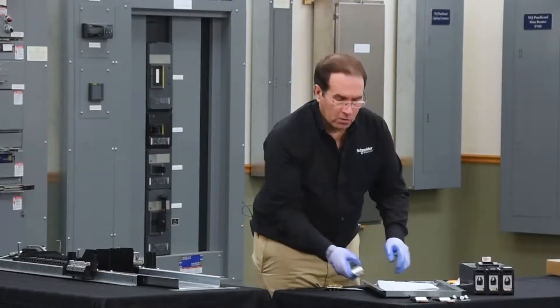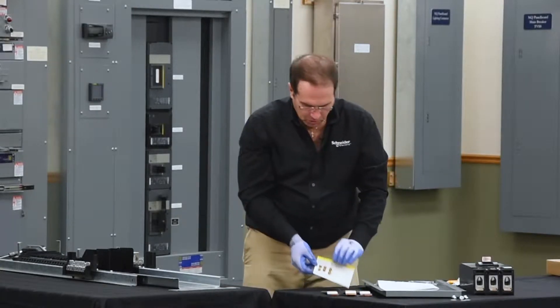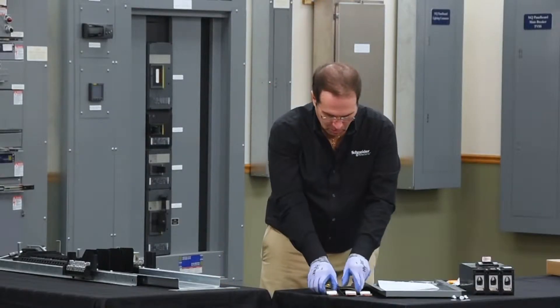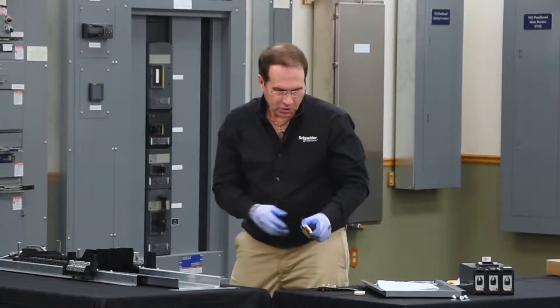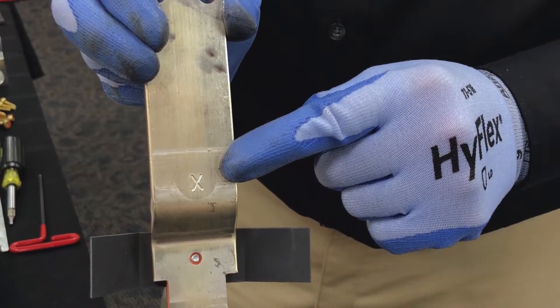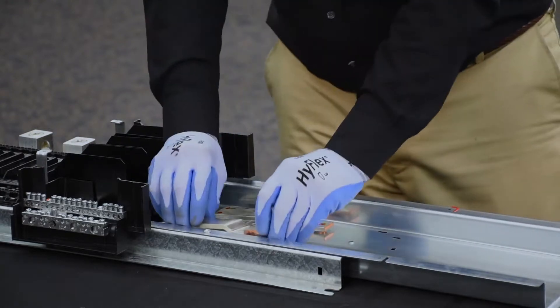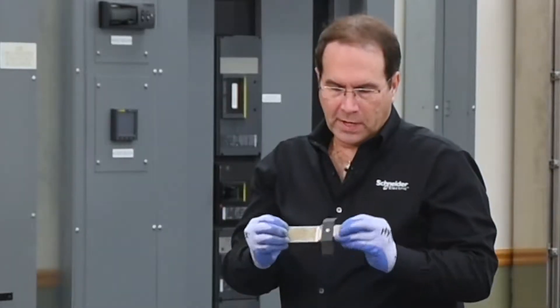The next step is to install the hard bus connectors onto the bus bars. These are attached utilizing the hardware from the hardware card. The hardware card also contains the required torque information. Each of the connectors is identified with an X on the top side. The B phase hard bus connector has an insulator.